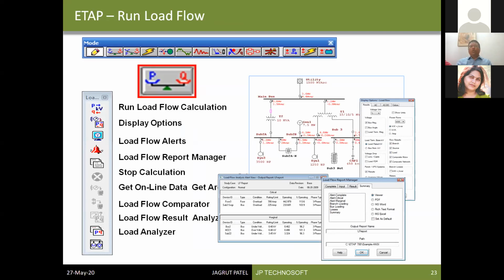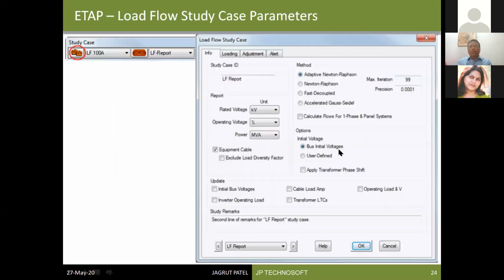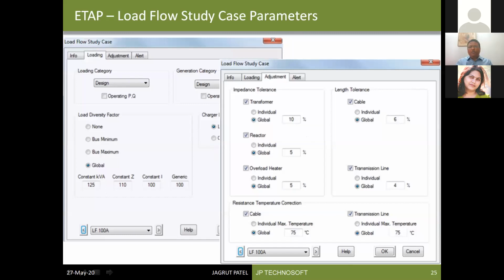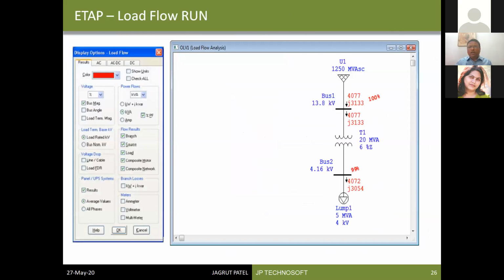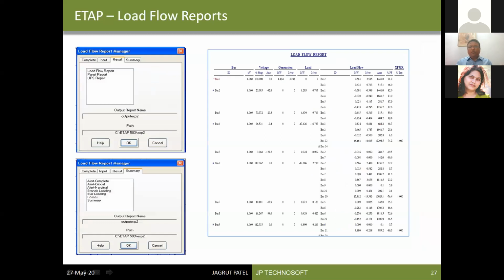So in the load flow study case, these are the settings which you need to make prior to performing the load flow. So you have to give basic information about the load flow. You have to select the rated voltage unit, you have to select the power unit, etc. Then there will be an adjustment requirement, whether your bus bar is suitable to handle the variation of voltage up to a 5% limit or 10% limit. All these limits you can set prior to performing load flow analysis. So load flow is done for a given circuit. You can also change the units given on this load flow diagram using these display options. And these are the reports which are generally available with every load flow calculation performance.